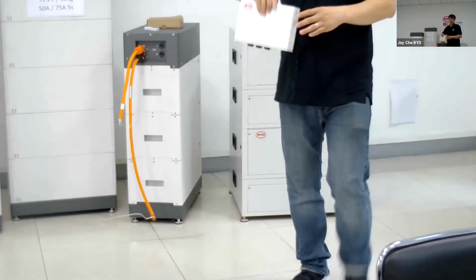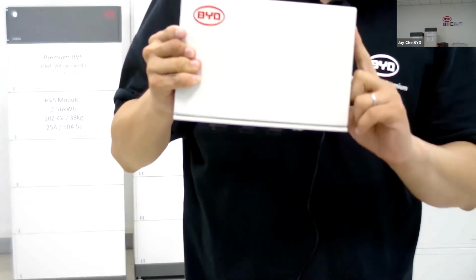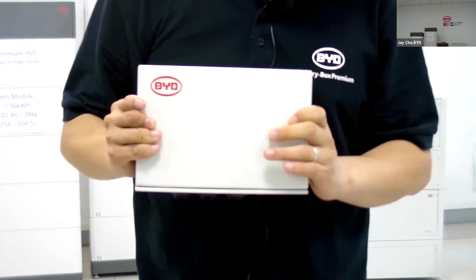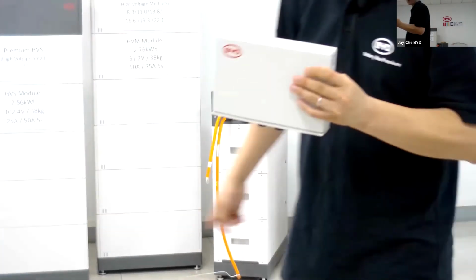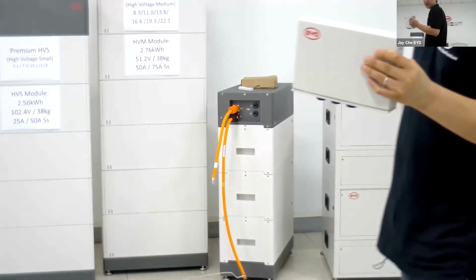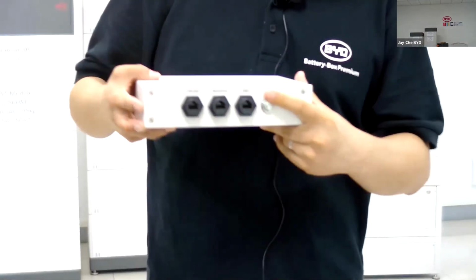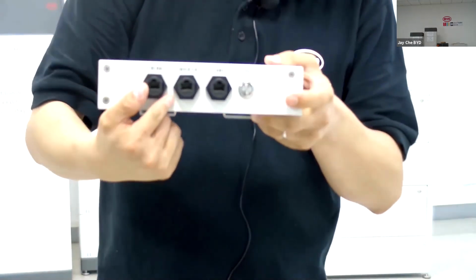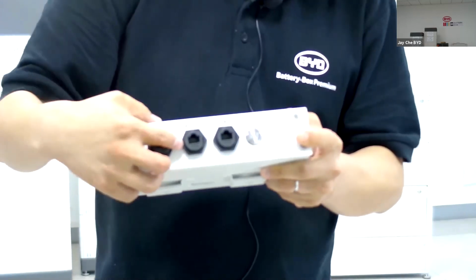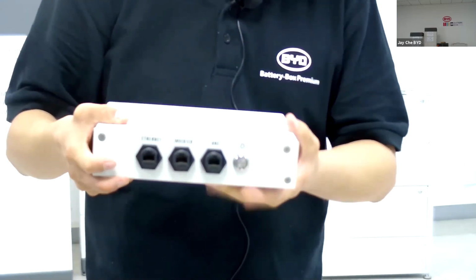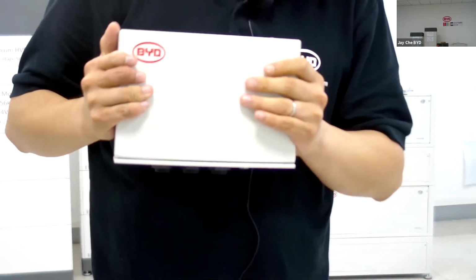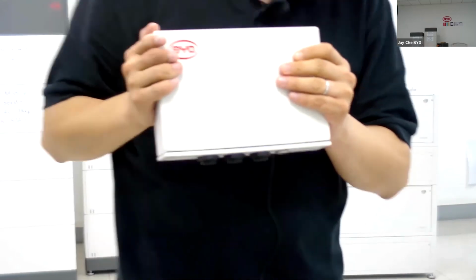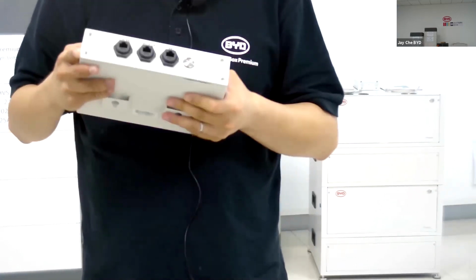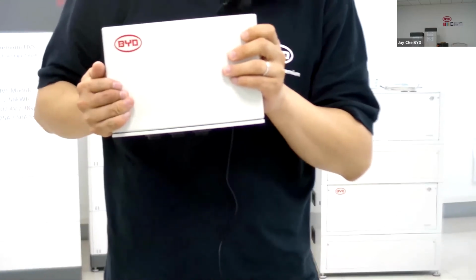One more thing I'd like to show you is, on the 48 volt range, we have this called the BMU, the battery management unit. This is only required for the 48 volt range, shown on the right-hand side. It's a communication unit, quite simple, basically talking to the batteries and the inverters, and it has a power button to turn on the system. You can think of it as a CAN box, required per system, like a level 2 communication and control of the system.